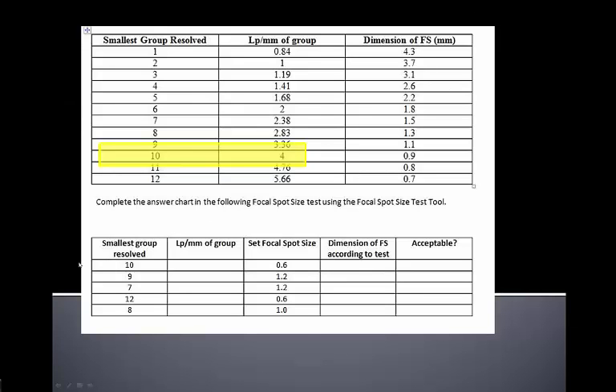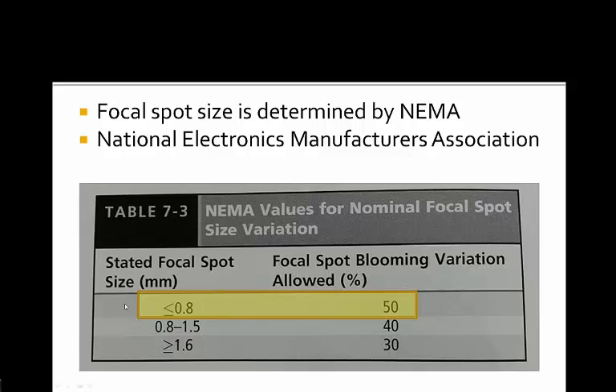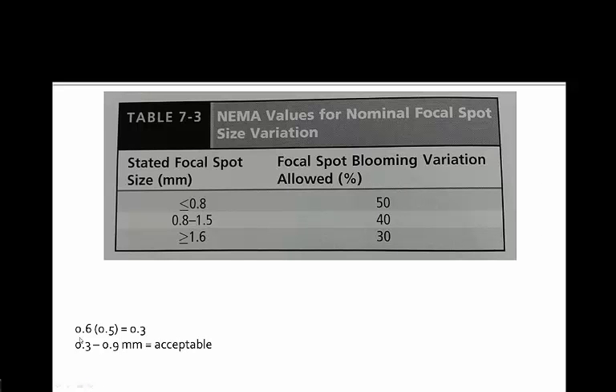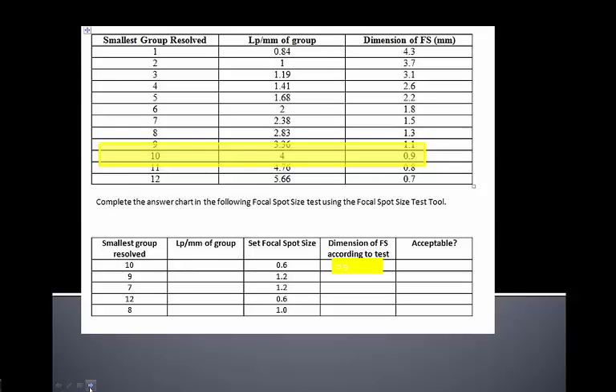Table 7-3 in your textbook is important for your exam. Focal spot size variation is determined by NEMA — the National Electronics Manufacturers Association. For focal spots smaller than 0.8 mm, the allowed variation is 50 percent. So if the nominal focal spot is 0.6 mm, 50% of that is 0.3 mm, meaning the acceptable range is 0.3 to 0.9 mm. In the earlier example where we measured 0.9 mm, that is just barely acceptable.